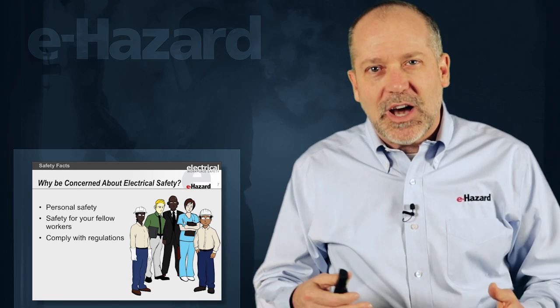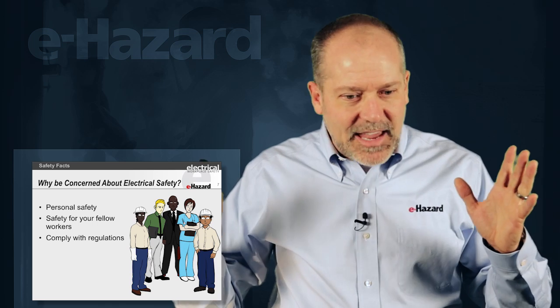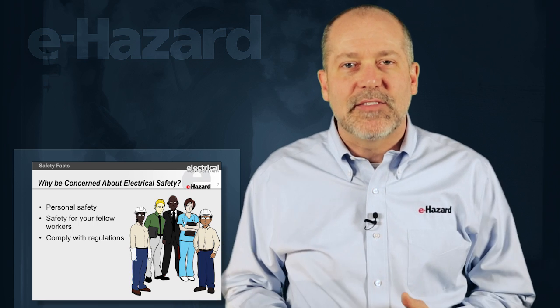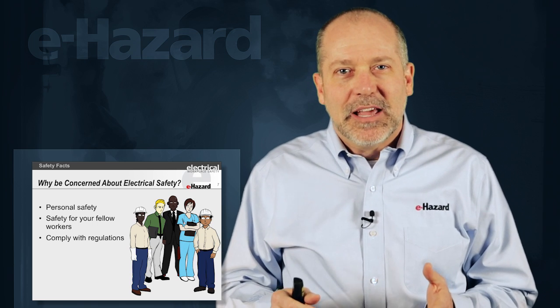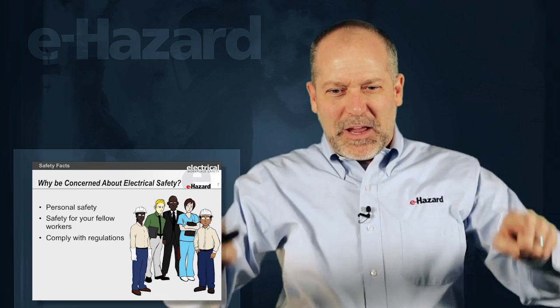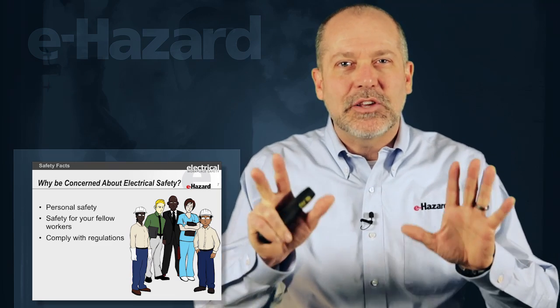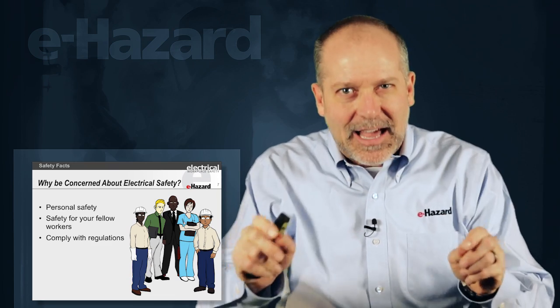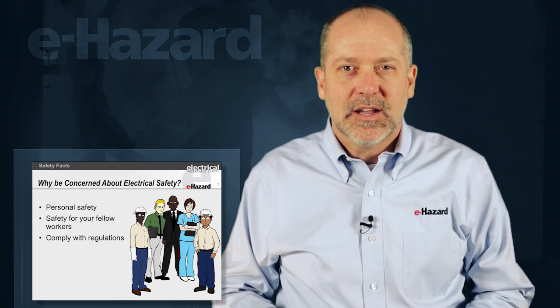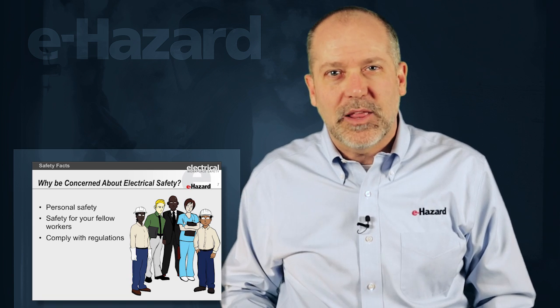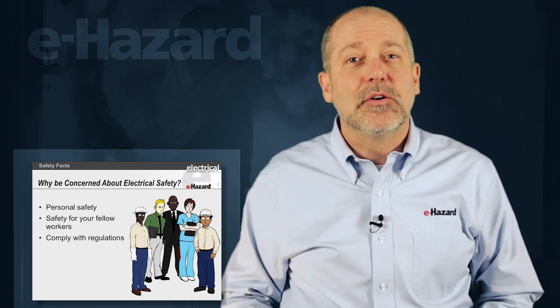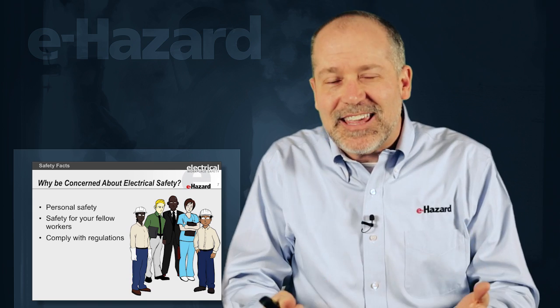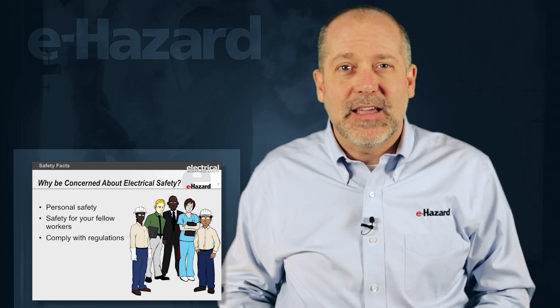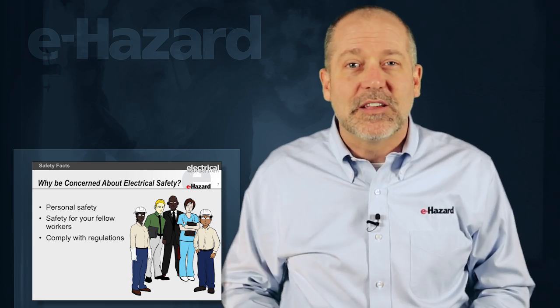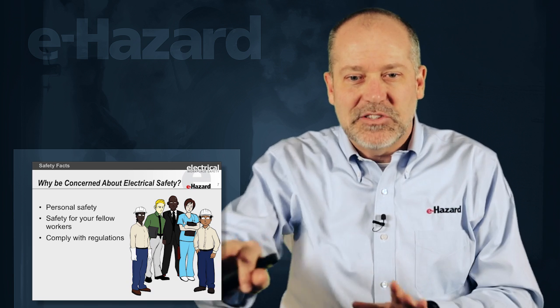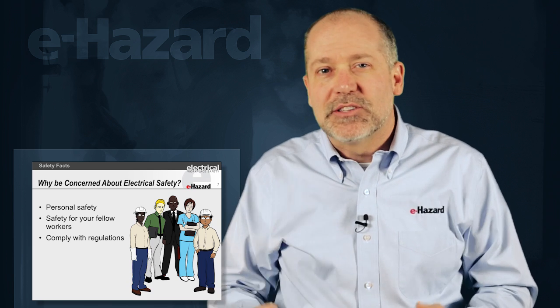As he's doing the job, cabinet open, he looks and can't find this CT anywhere. As he looks inside the cabinet, he sees an area about this big, a nylon cover, a black nylon cover with nylon screws on it. It's a dielectric cover with a warning label on it, the lawyers pointed out in the lawsuit, that said do not remove when energized. He was looking to see if the CT was behind that cover because he couldn't see it anywhere else. It actually was behind some other pieces of equipment, but he couldn't see it at the time.